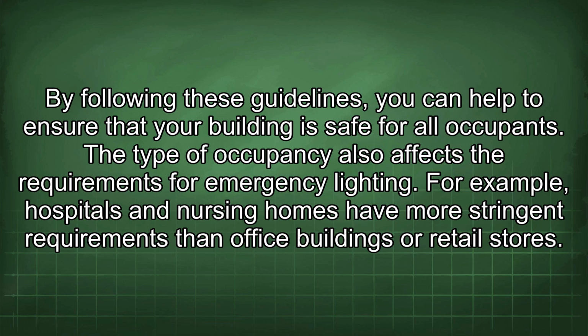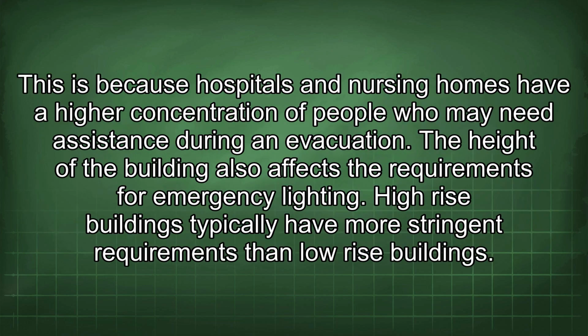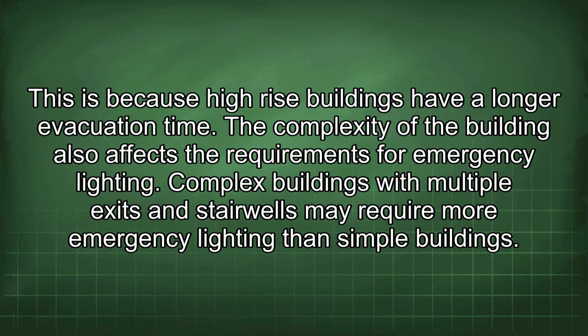The type of occupancy also affects the requirements for emergency lighting. For example, hospitals and nursing homes have more stringent requirements than office buildings or retail stores. This is because hospitals and nursing homes have a higher concentration of people who may need assistance during an evacuation. The height of the building also affects the requirements for emergency lighting. High-rise buildings typically have more stringent requirements than low-rise buildings. This is because high-rise buildings have a longer evacuation time.